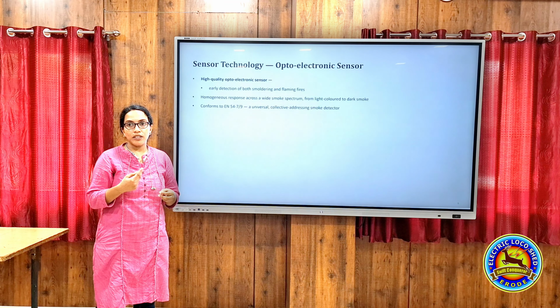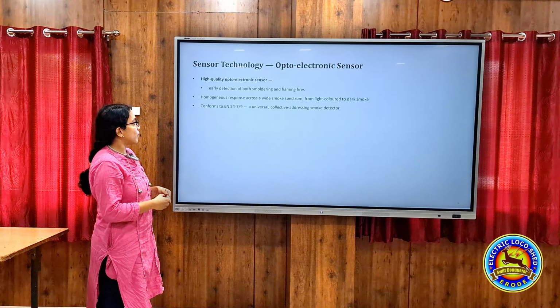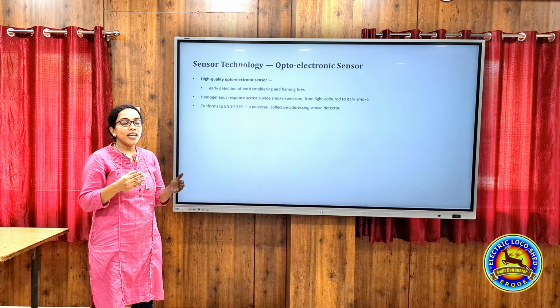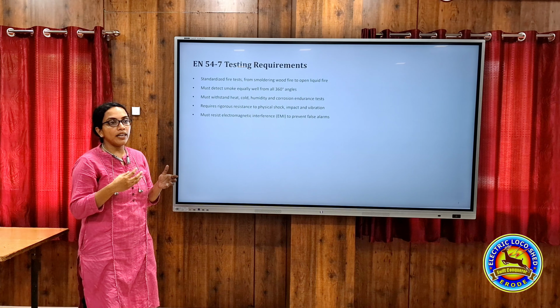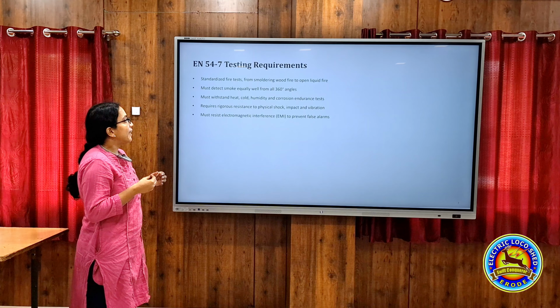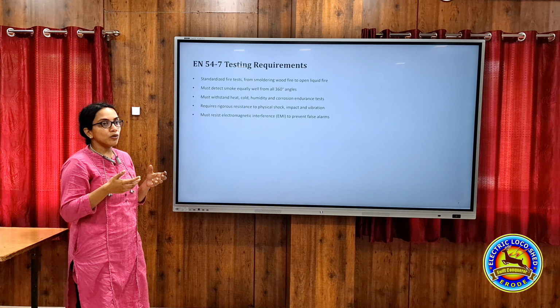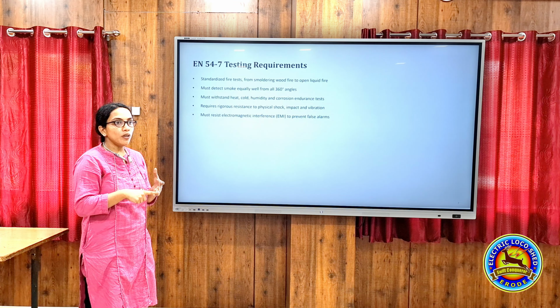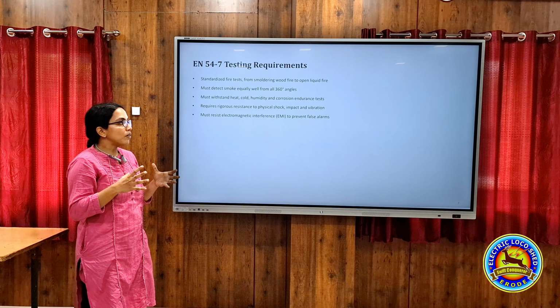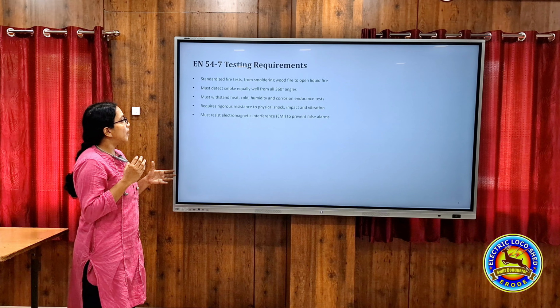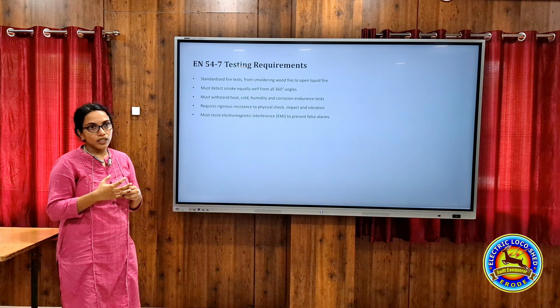As I said earlier, inside an FDU there are two sensors. We are using an optoelectronic sensor that should sense smoke from all types of smokes. The sensor should be according to the global standard EN 54-7. The standard is that it should be able to detect smoke like wooden smoke caused by wooden fire, up to open liquid fire. It should be able to detect smoke from all 360 degrees, and also be resistant to corrosion, heat, cold, and humidity. It should also be resistant to shock and vibration, and must also resist electromagnetic interference.